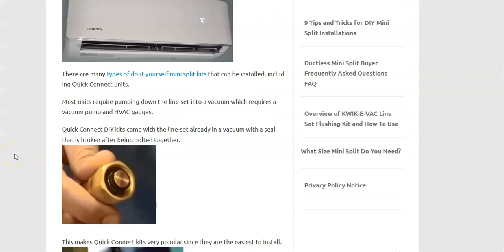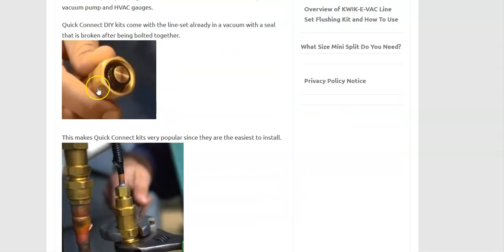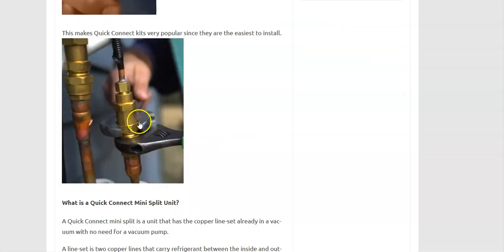The second option is to use what's called a quick connect mini split kit, and this is a very good option. Basically, these quick connect systems come sealed already. There's a seal at the end where you connect it, and that seal is only broken once it's bolted together, which is a very good system. It's widely used. When done correctly, it's just as good as vacuuming down the system since it's already in a vacuum.